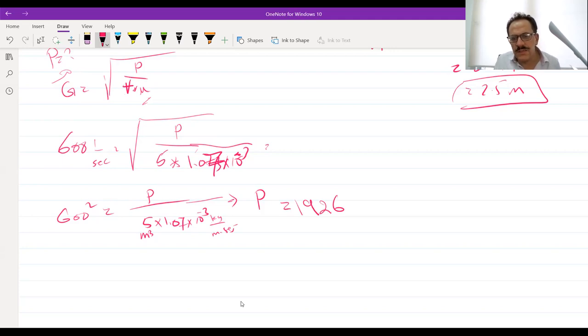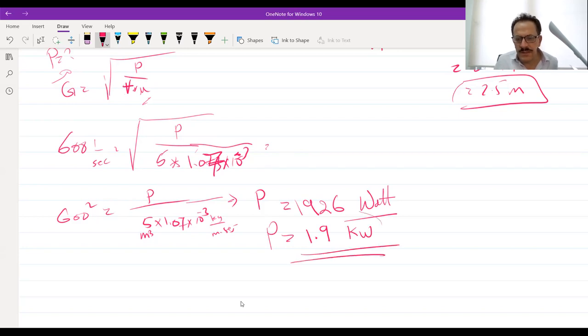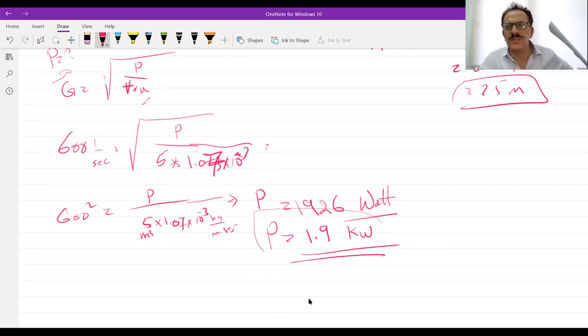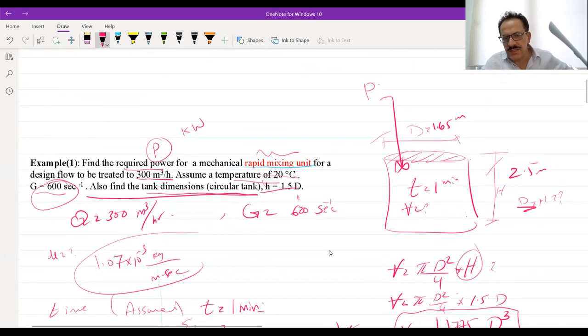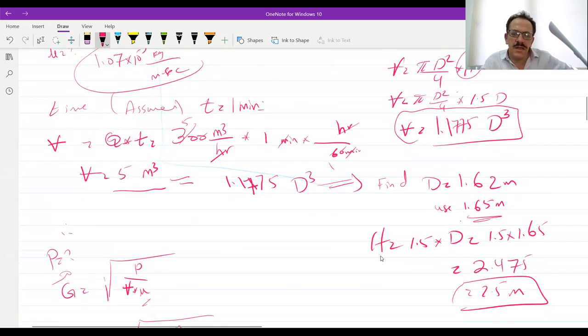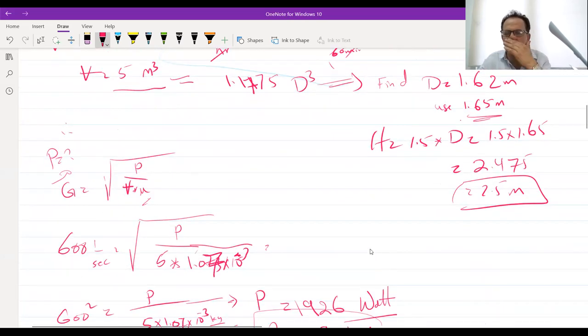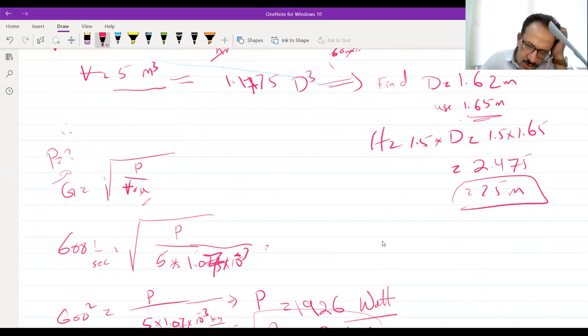So the needed power is 1.9 kilowatts. This means if you are looking for motor mixers, the power of the mixer should be not less than 1.9 kilowatts. That is for the case of only one tank. If you have two tanks, you divide the Q by two, and you need two mixers — one for each tank.